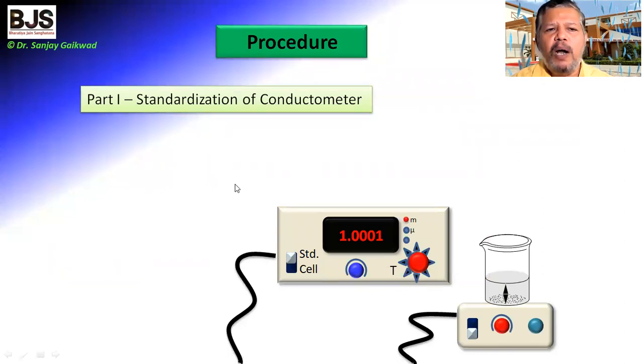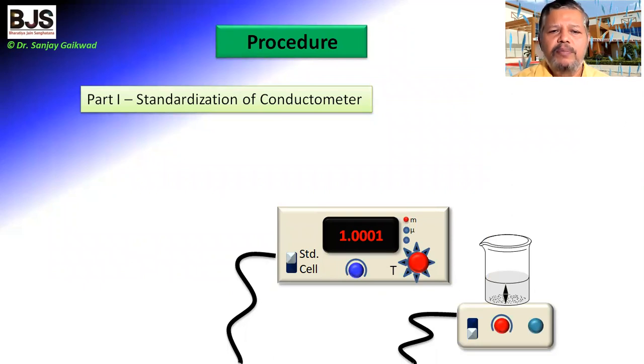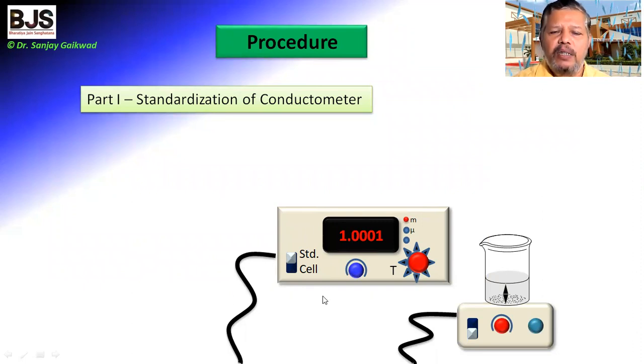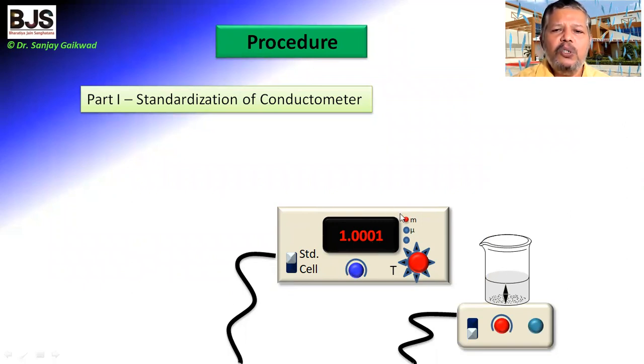In the first part of the procedure, there is standardization of the conductometer. For any determination or method, we have to standardize the instrument. We turn the knob on the standardization setting. Before starting the experiment, we have to switch on the conductometer for 15 minutes to allow a warm-up period for the display card as well as the indicator. The value displayed is 1.0001, with the knob set to milli.